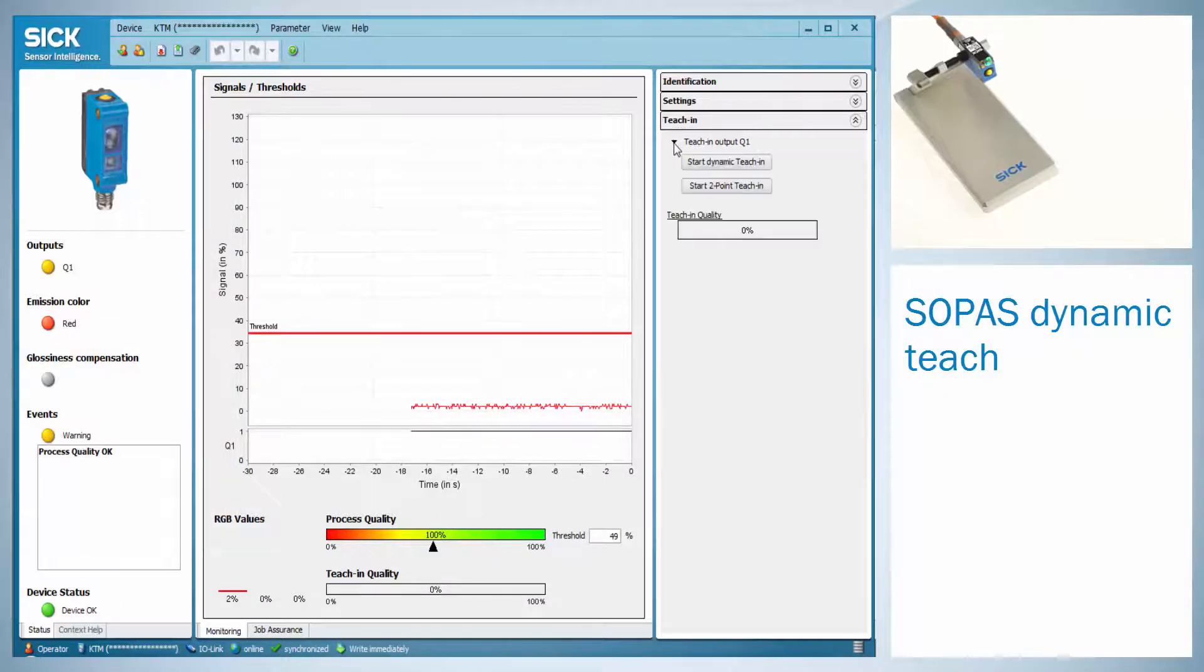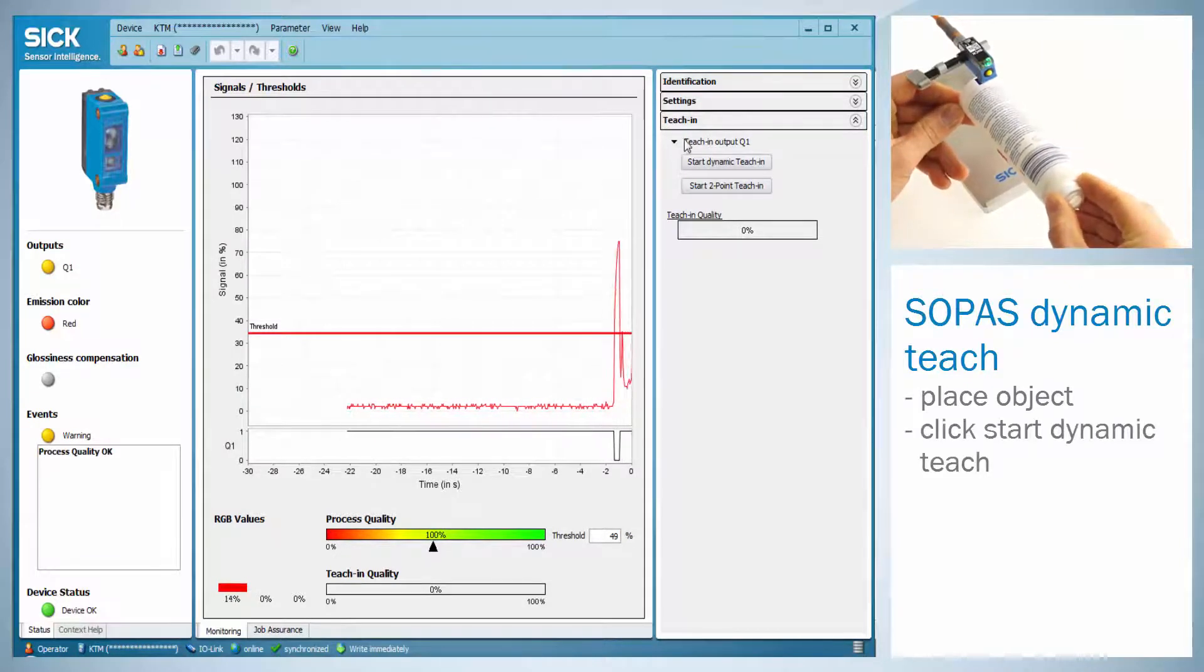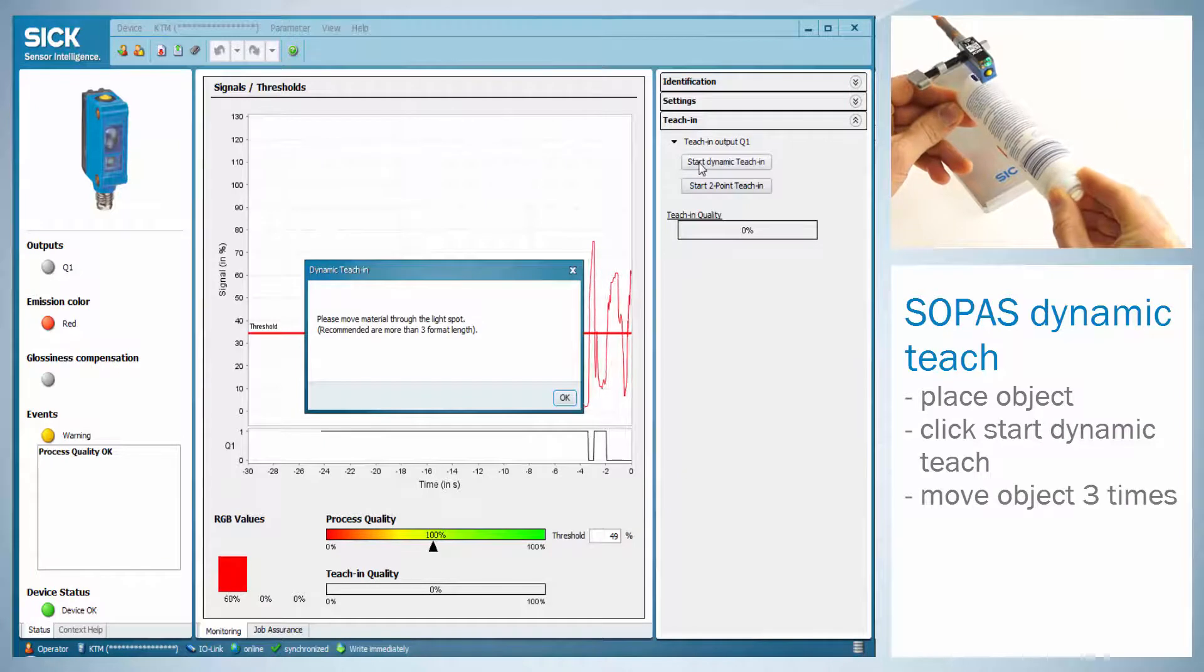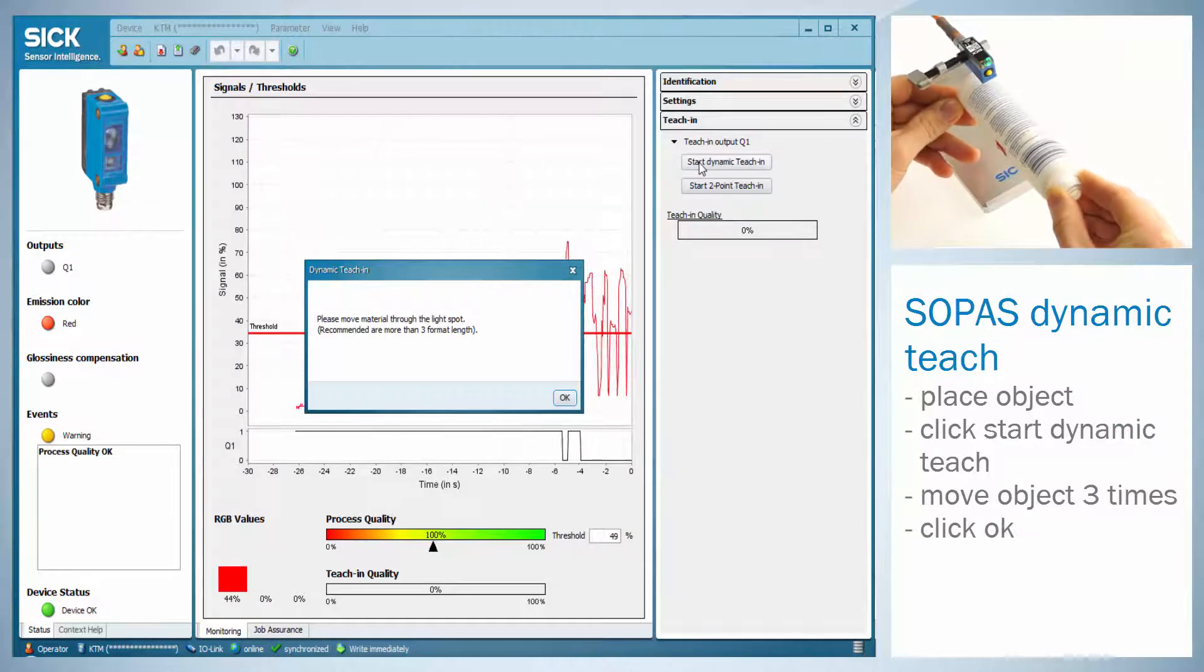The same applies for the dynamic teach. Place the object under the light spot, click the Start dynamic teach button, and move the object at least three times between mark and background. Click OK when you are finished.